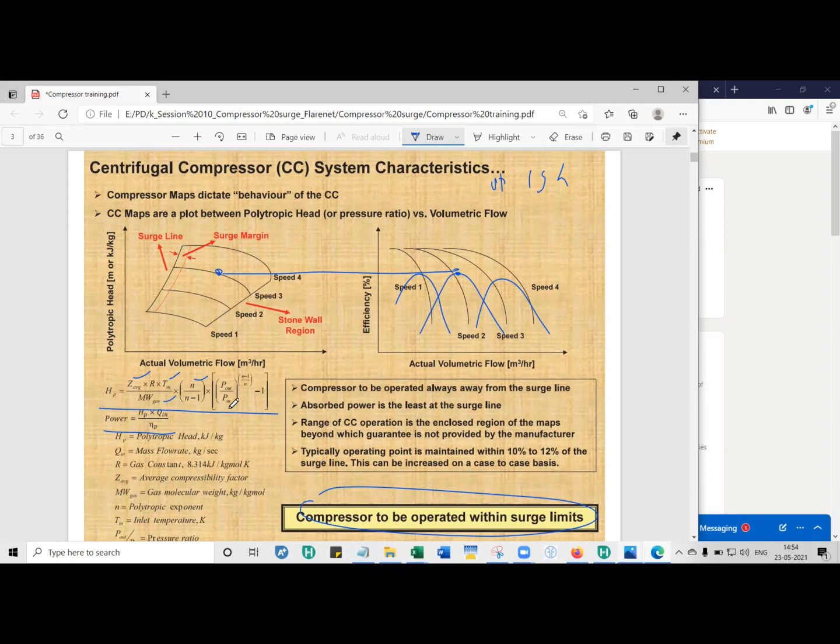Point number two, for a given set of pressure ratio and fluid parameters, for a given set of data, as the molecular weight of the gas increases, the polytropic head decreases and so does the power. And vice versa, so let's say you have methane and you have natural gas. Between methane and natural gas for the same pressure ratio, you need more power to compress methane, whereas natural gas has higher molecular weight, so it takes less power to compress it. So for a given pressure ratio, as the gas gets heavier and heavier, you will need less power to compress it.